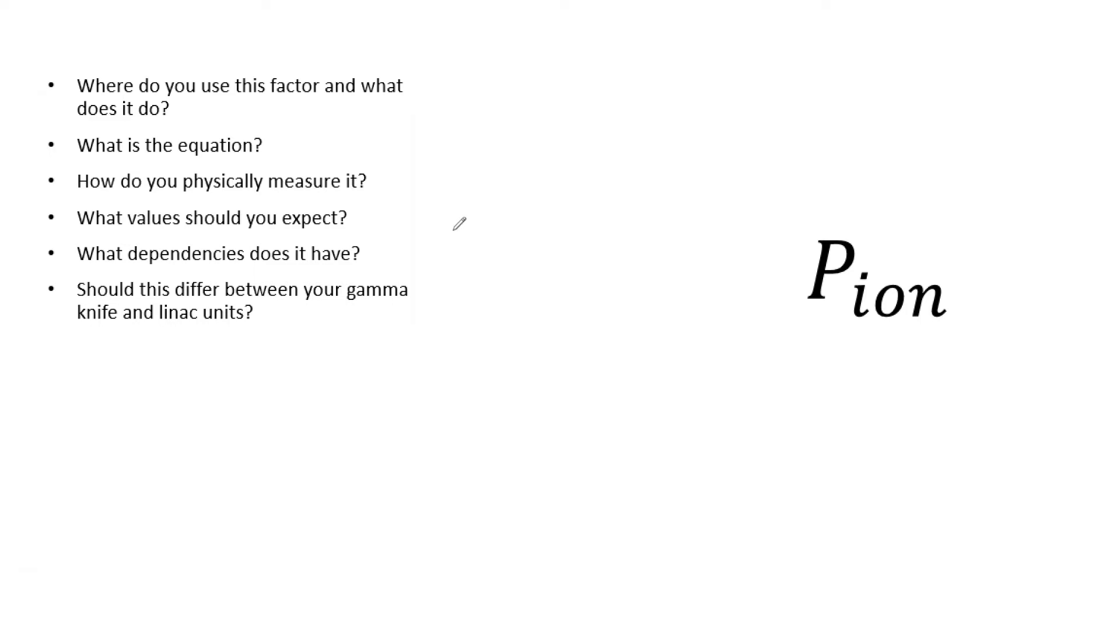So to begin, P ion is the ion recombination factor. It accounts for ion recombination in the chamber before ions are collected by the central electrode. You use it for TG51 or anytime you want to calculate what the dose is in a gas filled chamber.